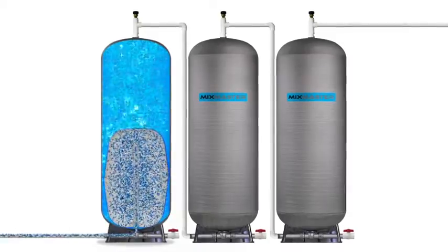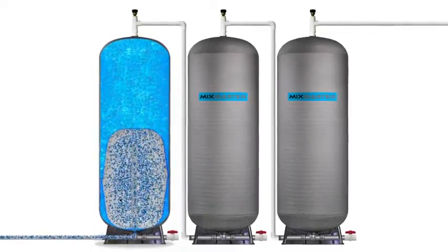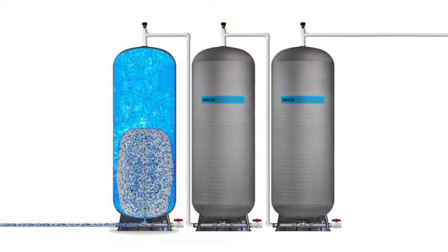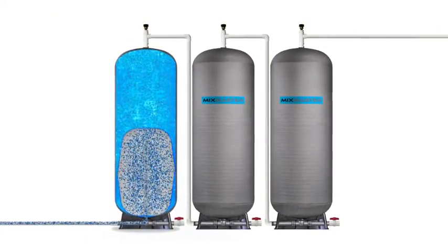This secondary mixing assures a thorough water-chlorine mix. It also helps achieve the proper contact time necessary to satisfy strict Board of Health requirements.